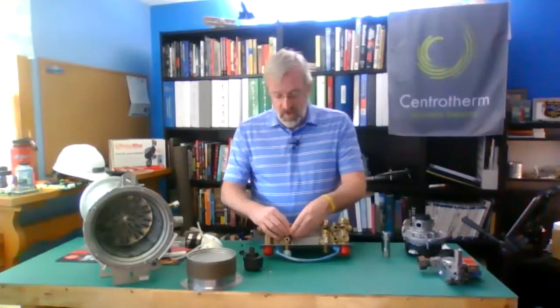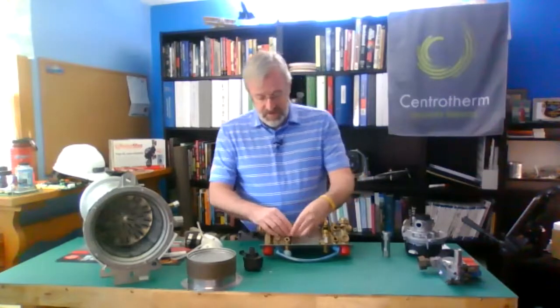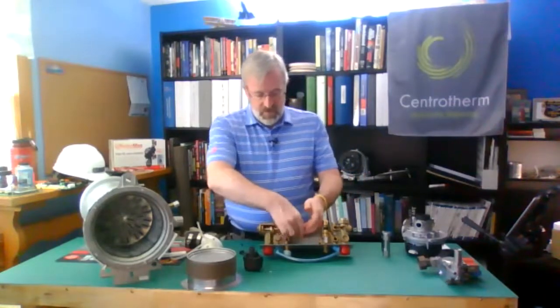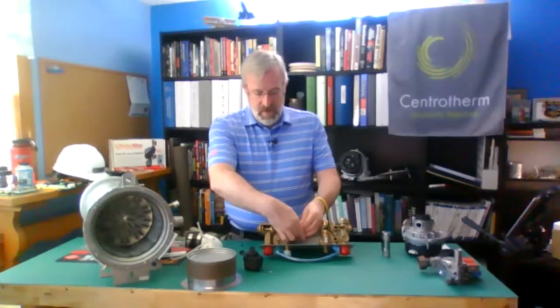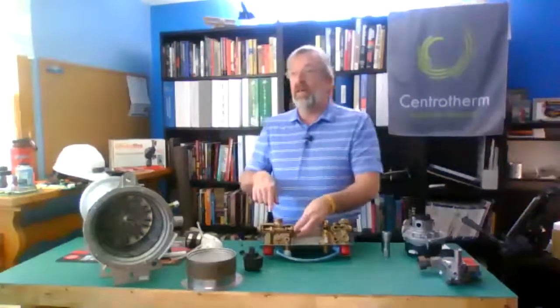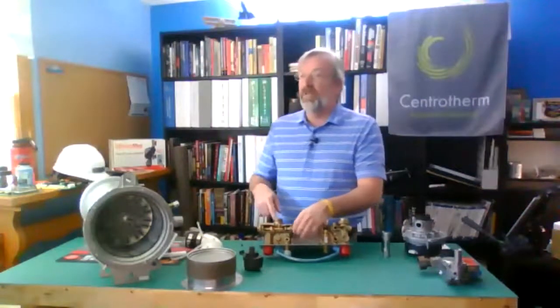Now, if you've got to clean that side, you've got an issue in your boiler water that you certainly want to take care of. Oops. Make sure you line it up. It's easy. I got to tell you, it's easy to line it up when I can look right down through the hole that won't be there when you're taking it apart in the field.